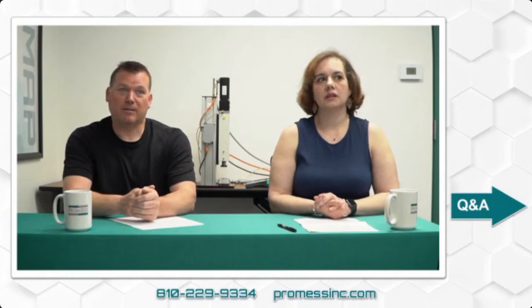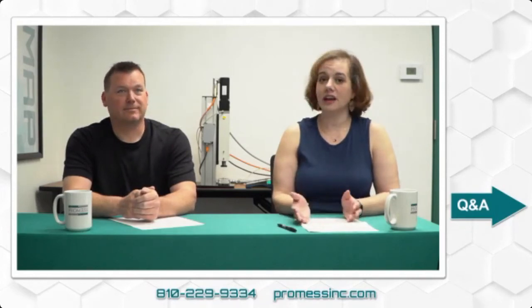It all goes back to the percentage of the range that you're using and how finite you can make those adjustments. If you're talking about 1 Newton meter on a 5 Newton meter torque pro, then it should be pretty good. If you're looking at a 50 Newton meter torque pro, it might be a little bit more difficult.